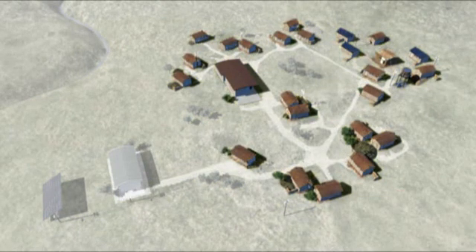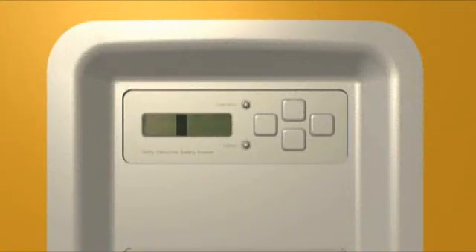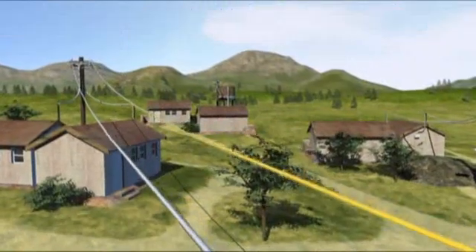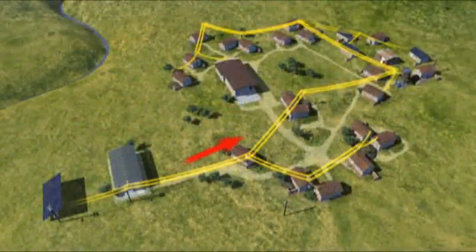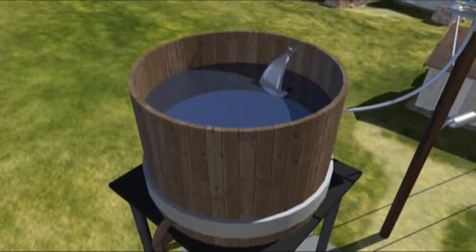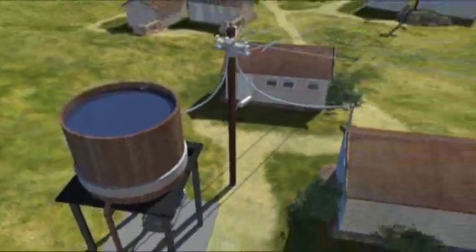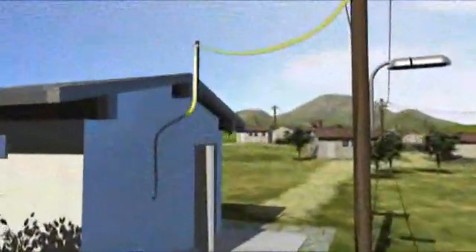Consumers and energy sources alike are coupled in a joint AC network. By minimally altering the network frequency and voltage, the Sunny Island battery inverter can regulate load fluctuations as necessary, in the same way as our public grid does. This means that at times when there is no direct demand for all the electricity available, it can supply special consumers such as water pumps or refrigeration systems.